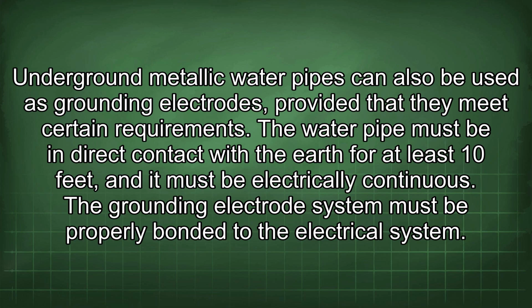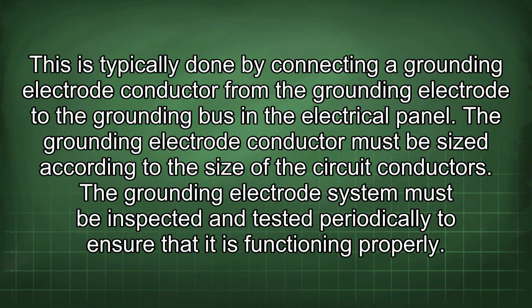The water pipe must be in direct contact with the earth for at least 10 feet, and it must be electrically continuous. The grounding electrode system must be properly bonded to the electrical system. This is typically done by connecting a grounding electrode conductor from the grounding electrode to the grounding bus in the electrical panel. The grounding electrode conductor must be sized according to the size of the circuit conductors.